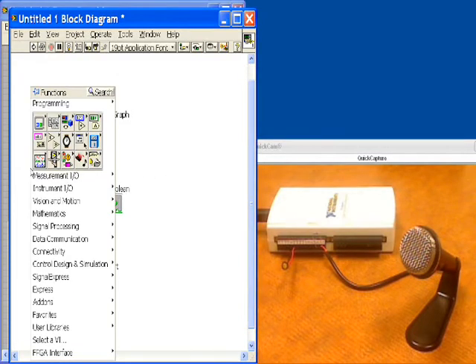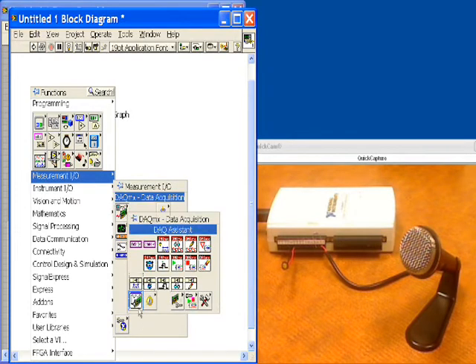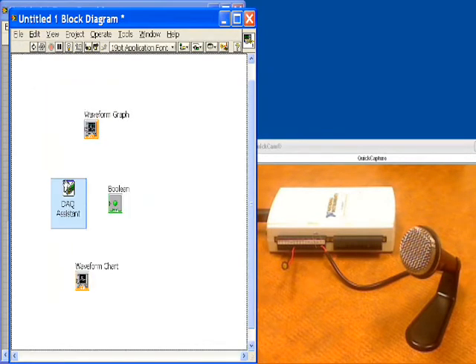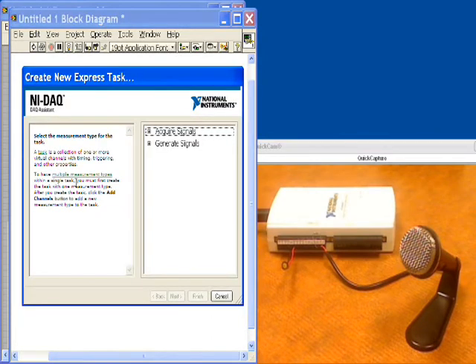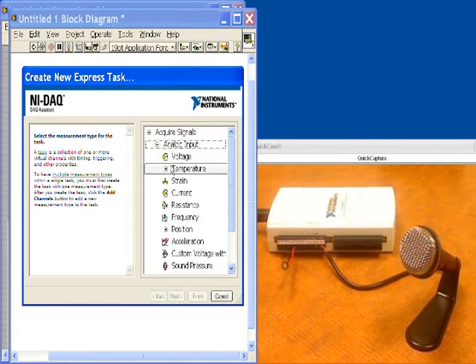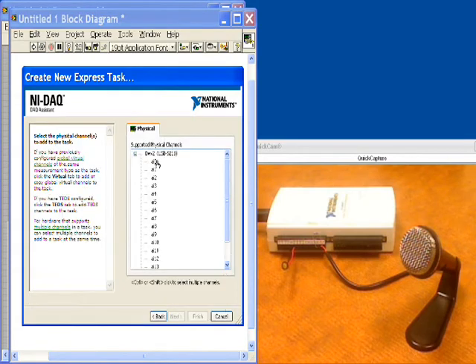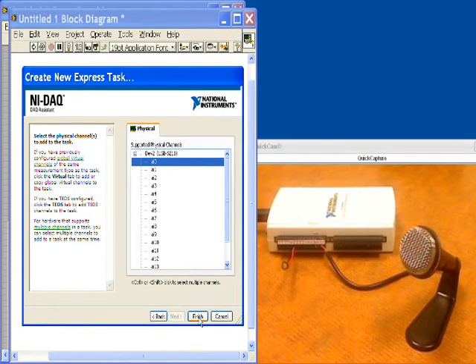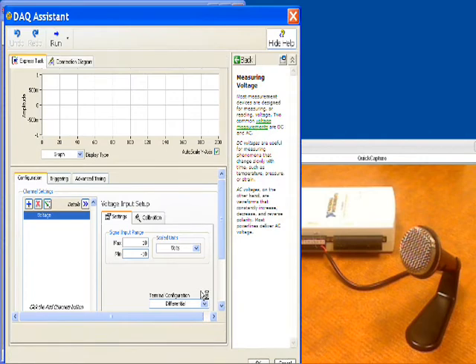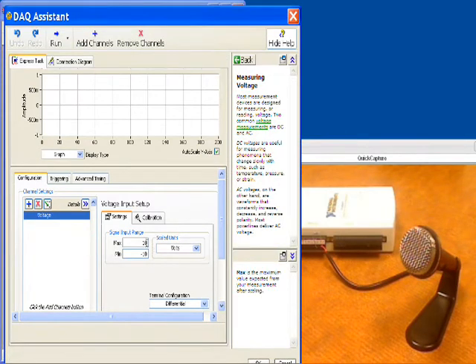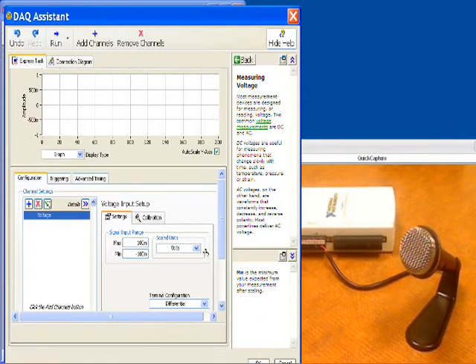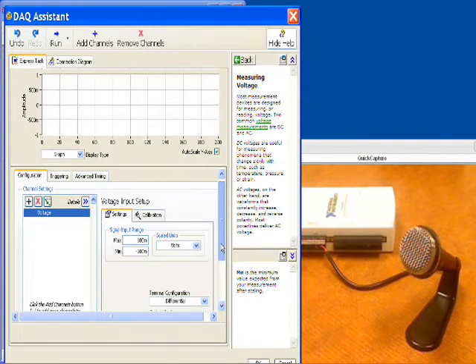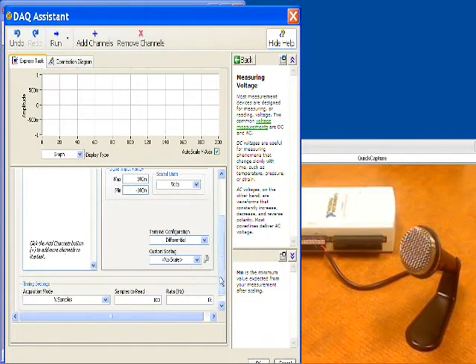First thing that we'll do is click the right mouse button and we'll get a DAQ assistant and we're going to set up our data acquisition. We're acquiring a dynamic signal so we'll have analog input, voltage. We'll choose it on our channel AI0 and we're going to acquire it at a bit higher rate. First thing we'd like to do is set the range. Since our microphone is not powered we're going to need to amplify that. We'll set it for plus and minus 100 millivolts and that will engage the onboard amplifier. It's already set up for differential ended mode so that's fine.